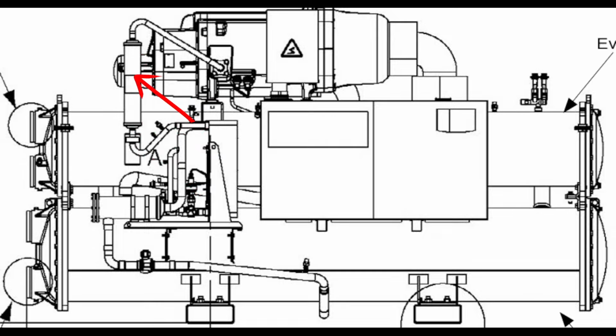I'm assuming this is a style of accumulator. Looking at this would be my assumption. So this is our economizer suction line coming back into the compressor. We're going to feed into a medium pressure port here at the compressor. So this pressure here is usually not down at an evaporator saturation level. This is like a medium pressure saturation, typically feeding into the compressor usually.